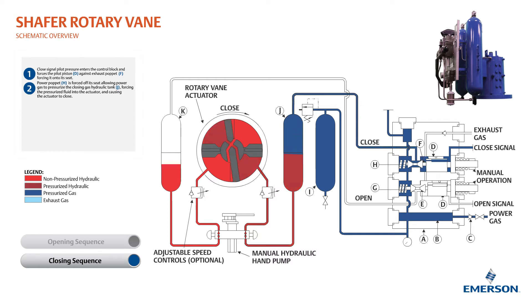This allows power gas to pressurize the closing gas hydraulic tank, forcing the pressurized fluid into the actuator and causing the actuator to close. The fluid displaced from the actuator flows into the opening gas hydraulic tank, which is open to atmosphere through the exhaust check valve in the poppet block.